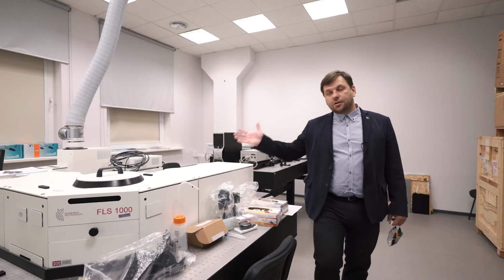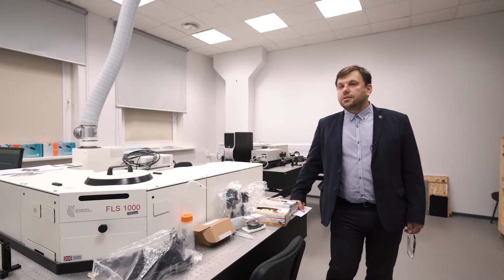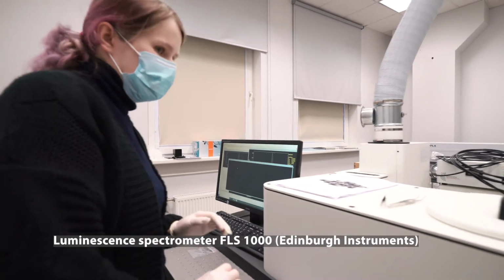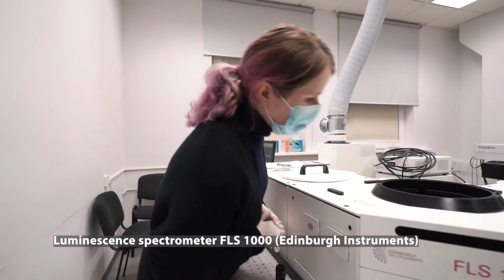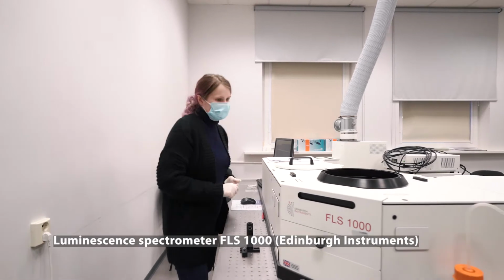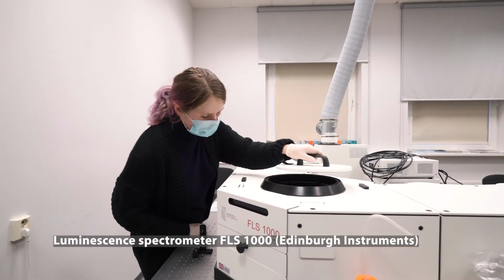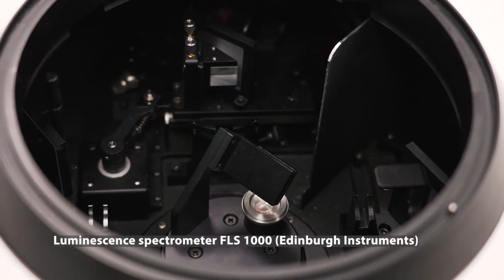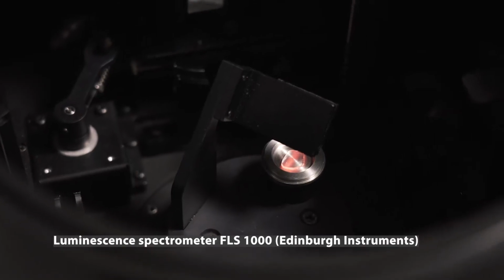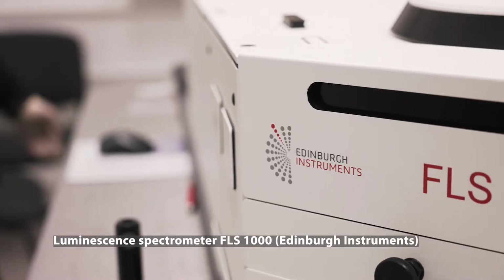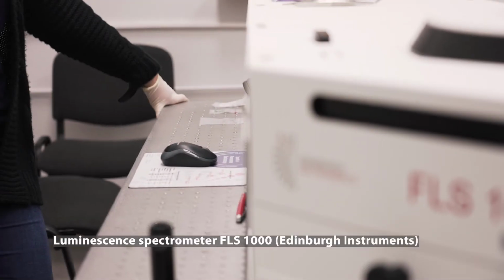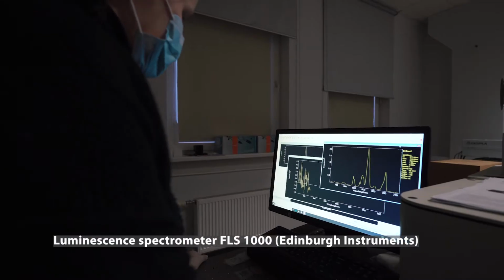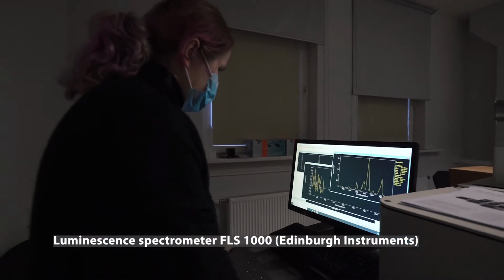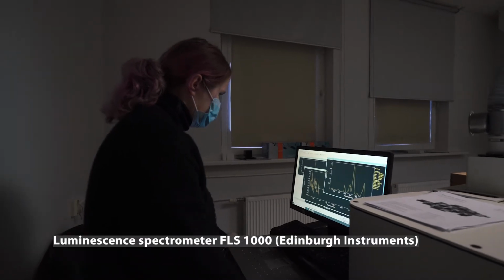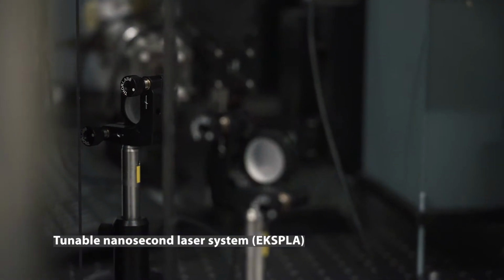For general characterization of the luminescence, an Edinburgh Instruments spectrometer is used. It allows a wide range of spectroscopic measurements, including luminescence spectra, luminescence excitation spectra, and luminescence decay kinetics measurements. Using an integrating sphere, photoluminescence quantum yield measurements can be performed. The spectrometer is widely used by different laboratories at the Institute, especially by projects studying materials actual for organic light-emitting diodes, materials and devices.